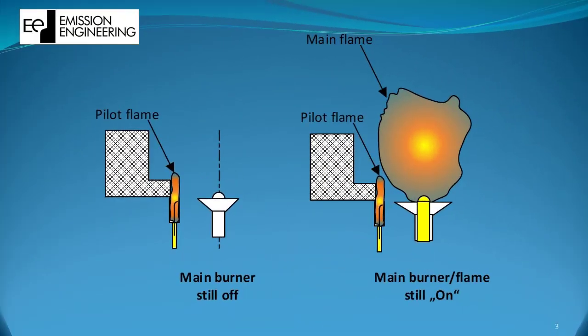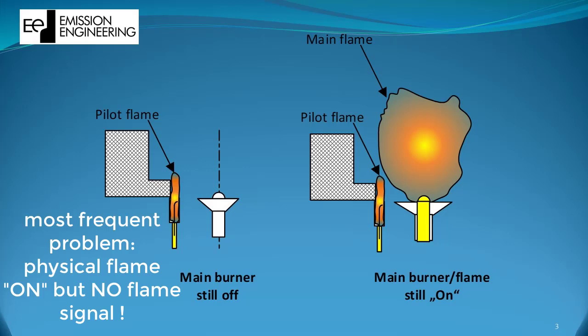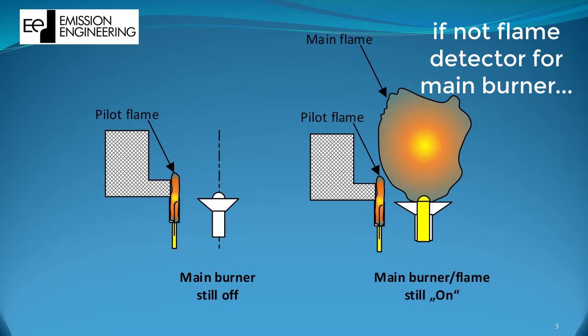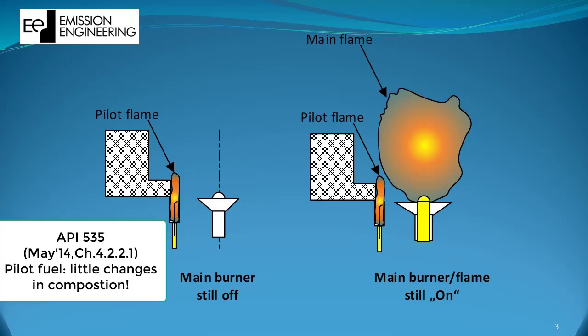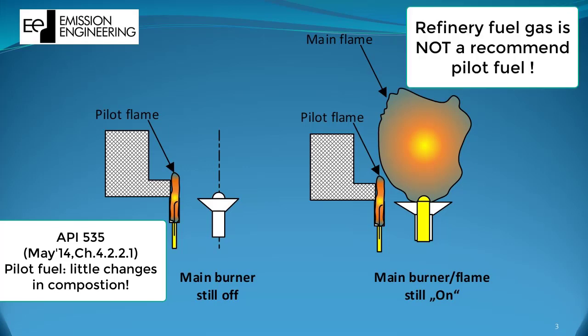There are several issues with pilots that can make trouble. Either it is a fail of the pilot flame signal or it is a lack of correct main flame supervision. However, keep in mind the recommended fuel for pilots as per API 535 May 14 is a fuel that varies little in composition like natural gas or propane. A refinery fuel gas with considerable change in hydrogen content is definitely not the preferred fuel, and many flame detection issues are caused by changes in fuel composition.